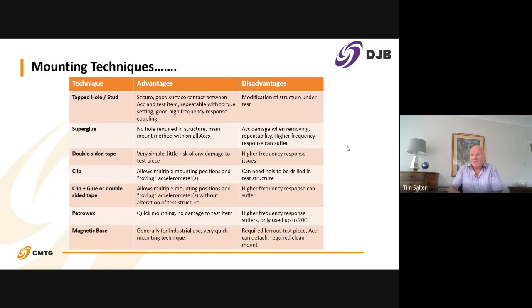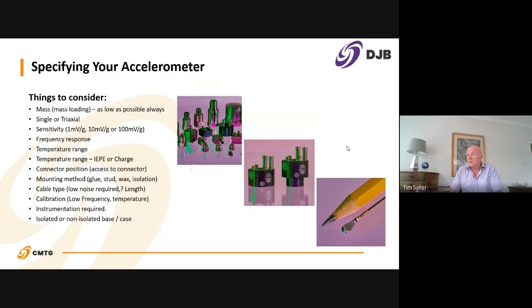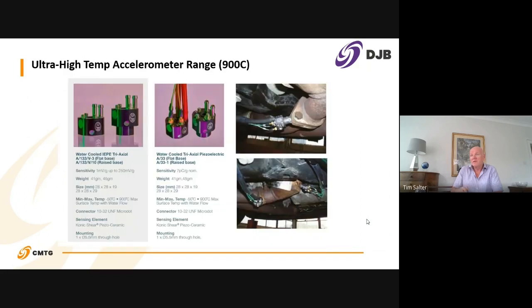Actually, let me just go back a slide, because I forgot to point out the ultra miniature accelerometer we do, which we believe is the world's smallest. You can see it in the bottom right here next to a pencil nib. So that really is very tiny, 0.19 grams, used in modal type applications. The water-cooled sensor, so another area where DJB are unique. You can generally go to about 450 to 550 degrees centigrade with a normal crystal type accelerometer. Then you can't really go above that without damage.